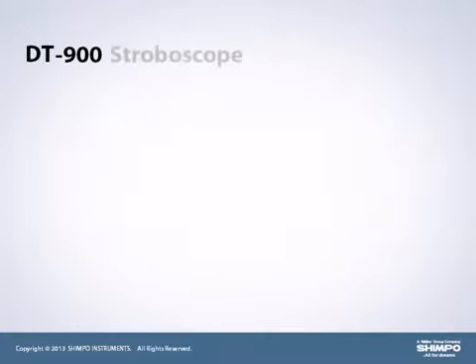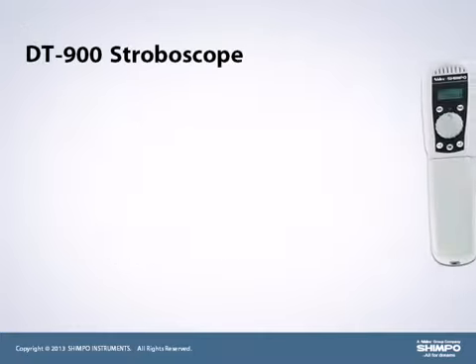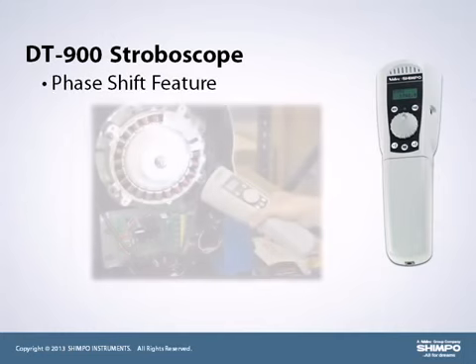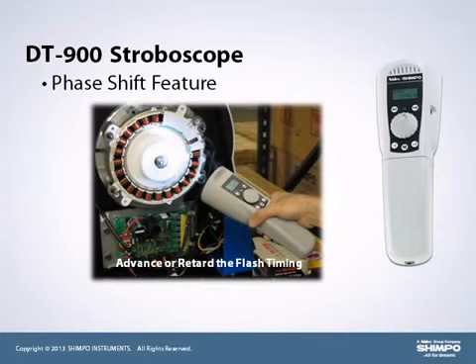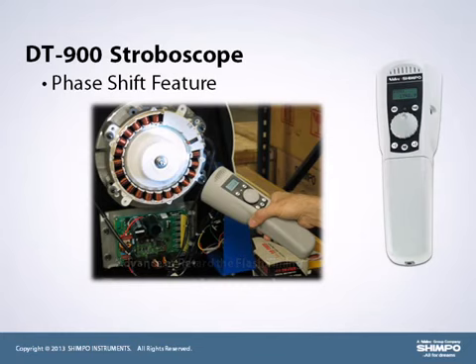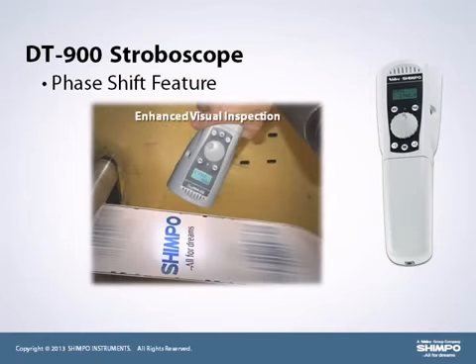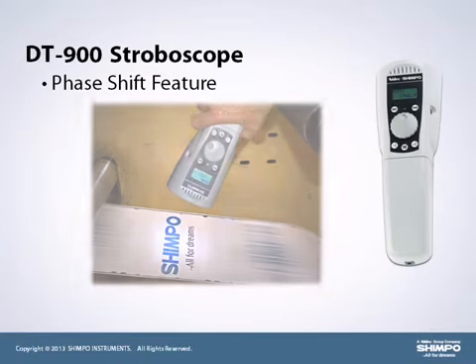The DT-900 stroboscope is the only palm-sized unit to include a phase shift feature. Phase shifting allows the operator to advance or retard the flash timing by degrees of angle, without changing the actual flash rate. The phase shift feature provides a frozen view of the rotating or reciprocating machinery for enhanced visual inspection of covered gear teeth, shafts, or ink injection patterns on print media.